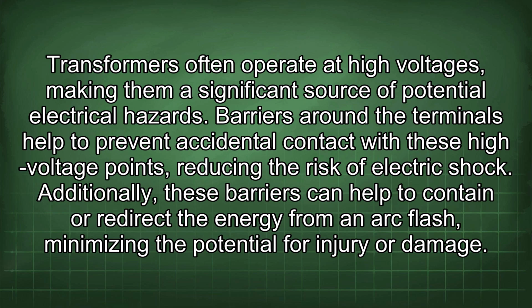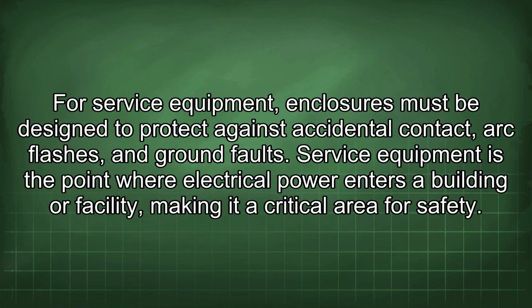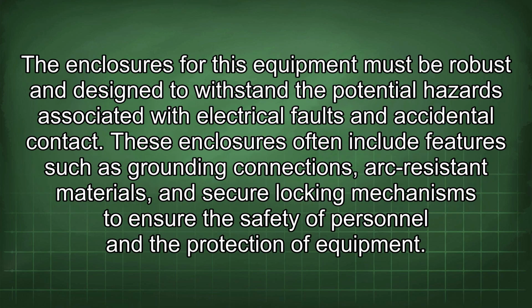For service equipment, enclosures must be designed to protect against accidental contact, arc flashes, and ground faults. Service equipment is the point where electrical power enters a building or facility, making it a critical area for safety. The enclosures for this equipment must be robust and designed to withstand the potential hazards associated with electrical faults and accidental contact. These enclosures often include features such as grounding connections, arc-resistant materials, and secure locking mechanisms to ensure the safety of personnel and the protection of equipment.